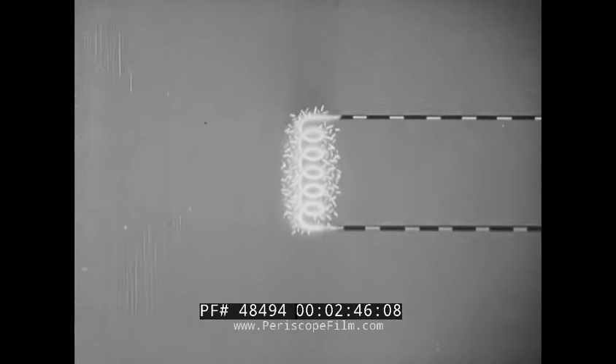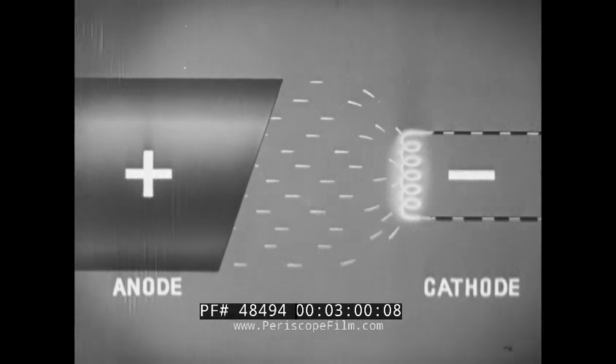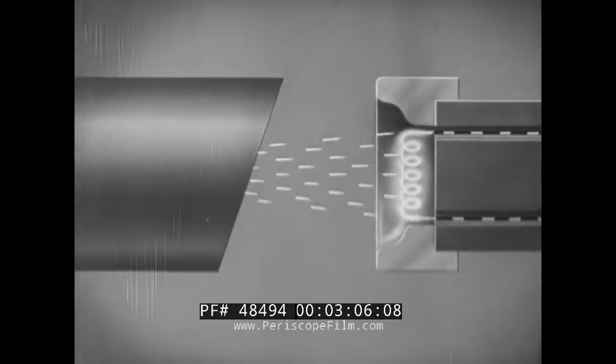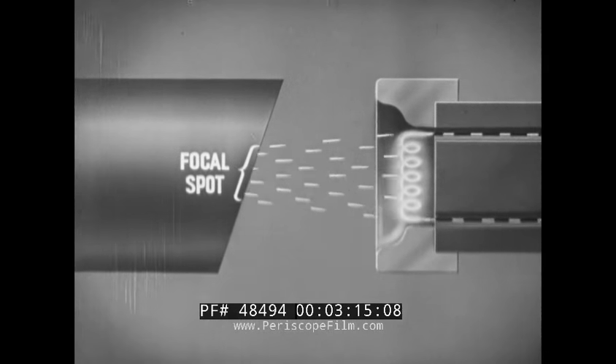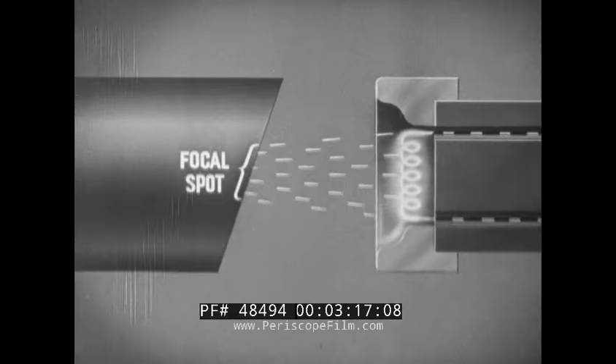The source of the electrons is a wire filament. When it is electrically heated, negatively charged electrons are released. If we connect this filament as a cathode or negative pole and introduce a positive pole, an anode, the negatively charged electrons will speed toward the anode. A focusing cup around the filament concentrates the flow of electrons on a small area of the anode. This is called the focal spot. The smaller the focal spot, the sharper the x-ray image.